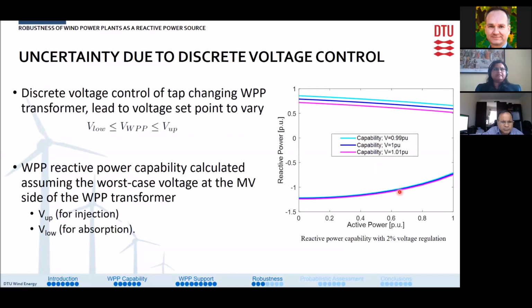Dealing with the uncertainty from the discrete voltage control action first, we know that the taps are discrete in nature. So the voltage set point of the tap changing transformer can vary between an upper and lower bound. For example, if the voltage set point is 1 pu and there is a 2% voltage regulation, then the lower and upper bounds of the voltage will be 0.99 pu and 1.01 pu respectively.